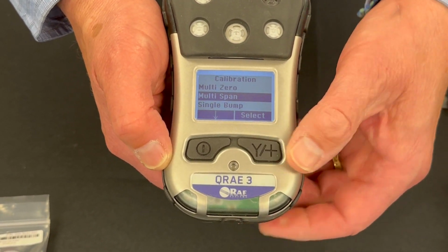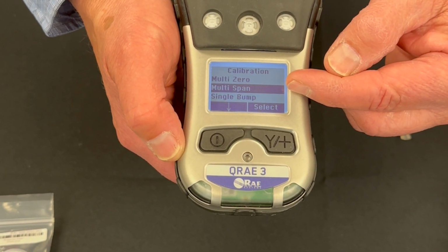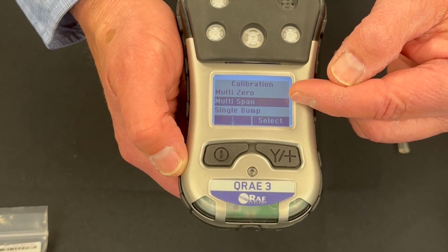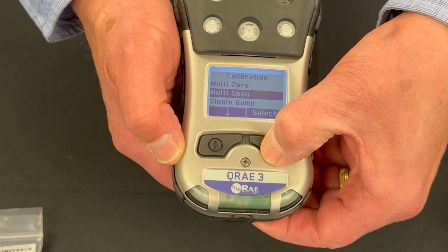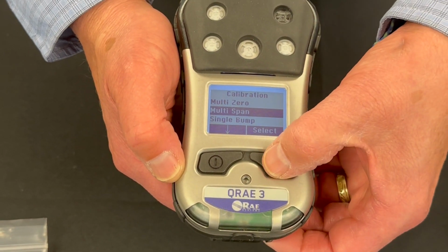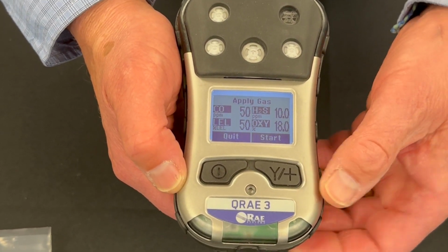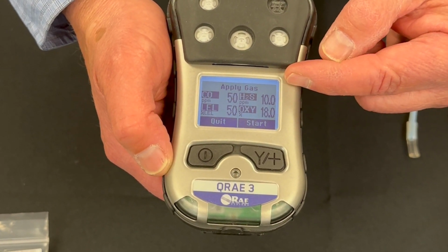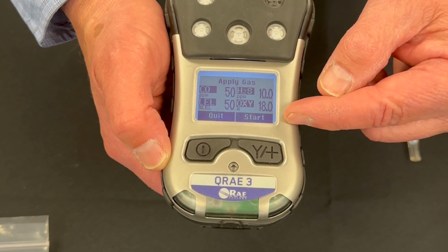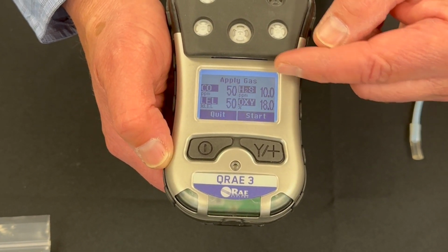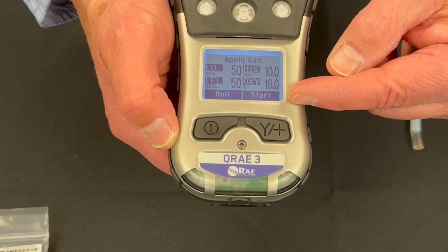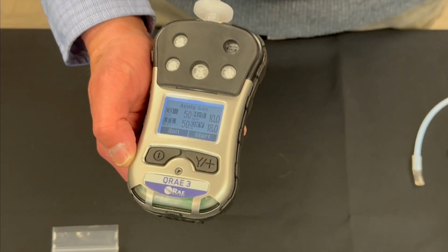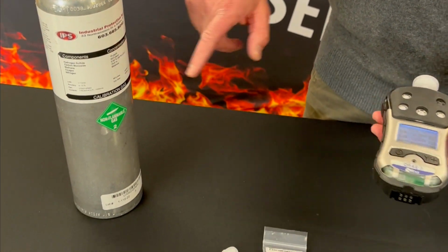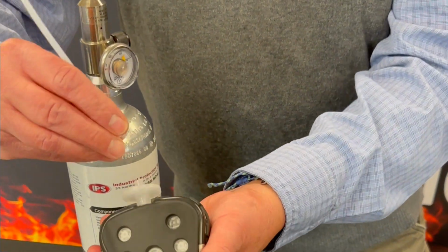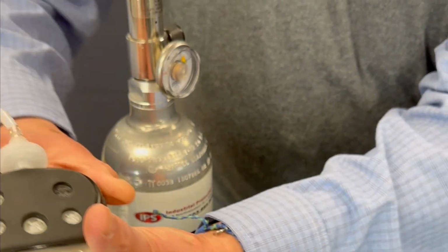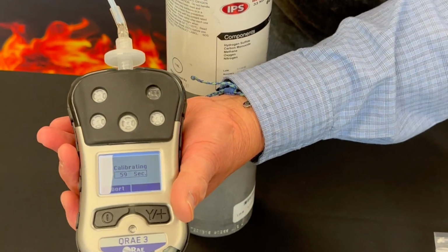I now hit exit, and it automatically defaults and jumps to the next option, which is my multi-span, my multi-gas span. I'm going to hit select. It gives me my calibration values. I want to take a second, if this is my first time doing it or I haven't done it in a while, to confirm that the values in my calibration menu on the instrument match what's on my calibration gas cylinder. If that is all good, I can make the hookup, start, introduce my gas.